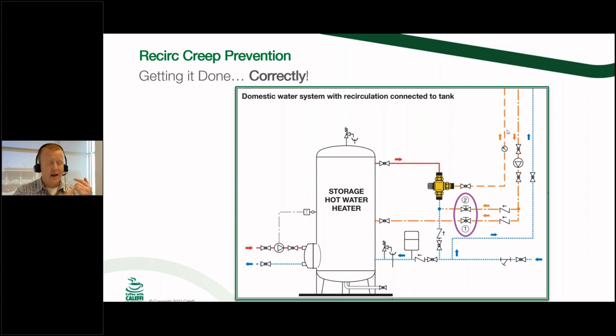You're going to need your domestic hot water system up and running. You're going to need a fully functional recirc system that's perfectly balanced like it should be. And then from there, you're going to need a time where you have next to no demand or no demand from your domestic hot water system or your potable water system. So you're either going to be doing it while the building's completely unoccupied or in the middle of the night and things like that. So it really turns into an interesting thing, because it's kind of difficult to do, because again, you've got to have this really specific set of circumstances.